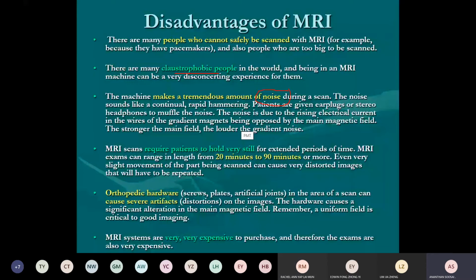The electromagnet noise, I think. You can't stay inside without earplugs. You must have earplugs. Okay. If not, it's so noisy. The noise sounds like a continuous hammering sound. Yes, sometimes a hammering sound. Patients are normally given earplugs or stereo headphones to muffle the noise. The noise is due to the rising electrical current in the gradient magnet wires being opposed by the magnetic field. The electromagnet causes the noise. Okay.